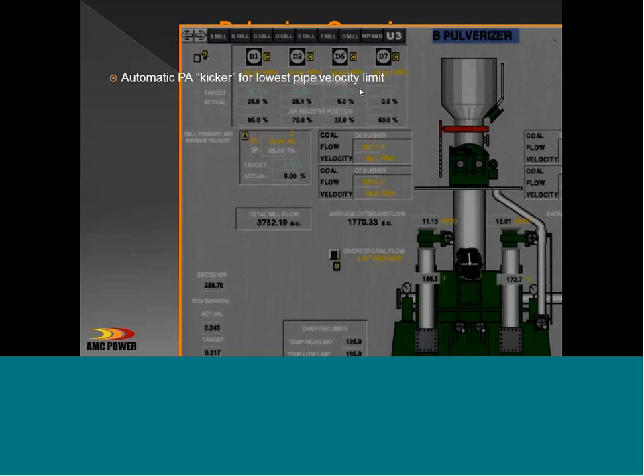And the set point says, if we get below this set point, and this particular plant, it's programmable, this particular operator wants to use 65 feet per second. If any pipe goes to 65 feet per second, this is the control. A primary air kicker is introduced so that the primary air on this mill will be increased by this amount. And again, it's programmable. They use 5%.